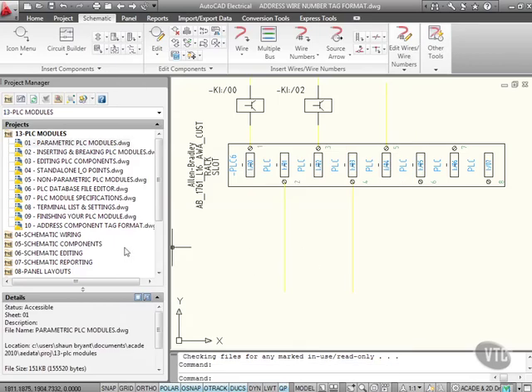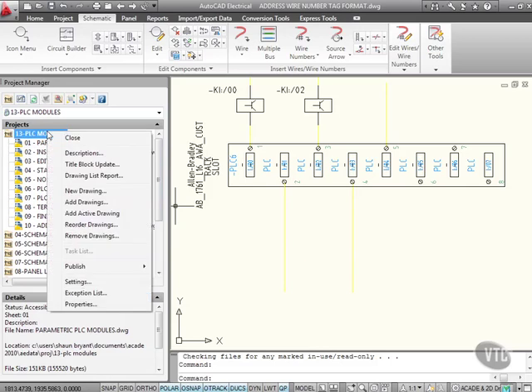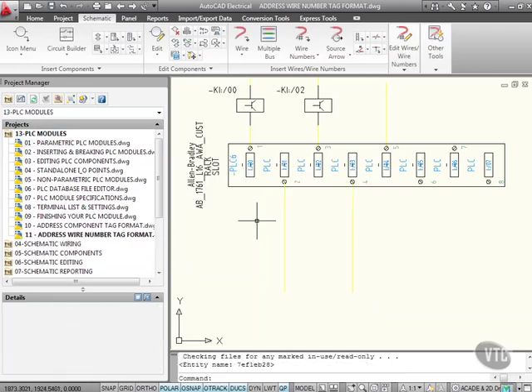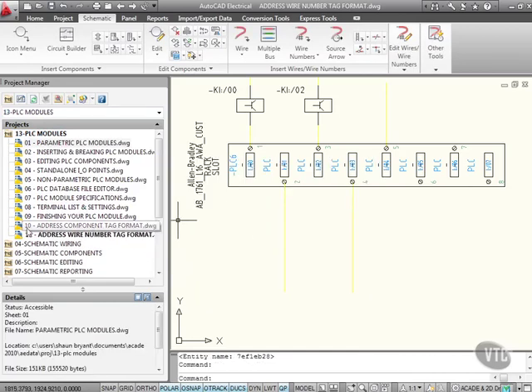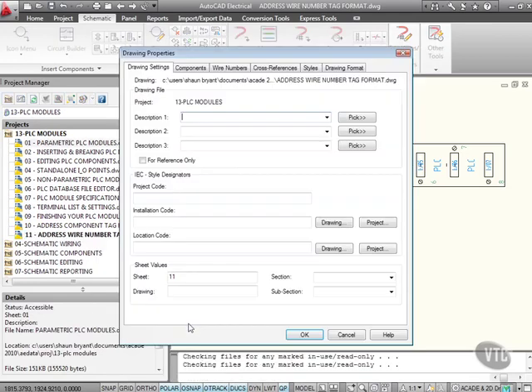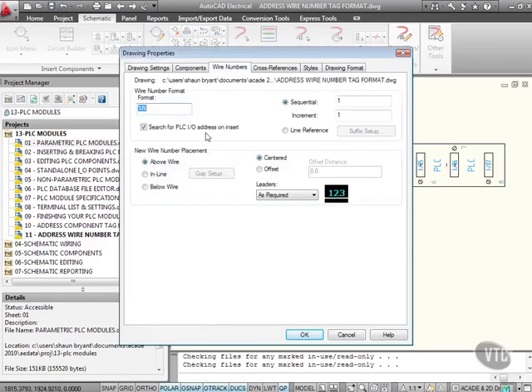I now need to add my drawing to the project. Right click, add active drawing. Do I want to apply the project default values to the drawing settings, the current drawing? Yes, I do. So there's number 11, address wire number tag format. If I right click on that and go to properties and drawing properties and look at wire numbering, again, it's searching for the PLC input output address on insert.